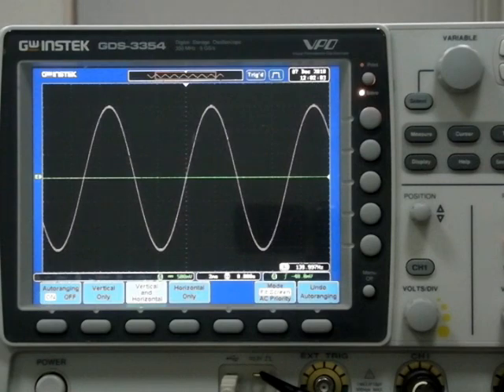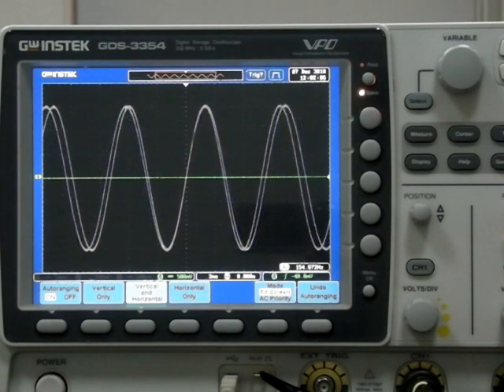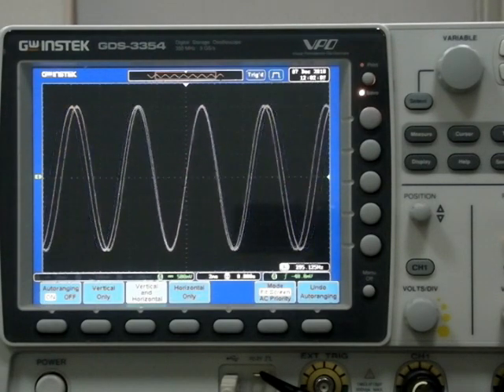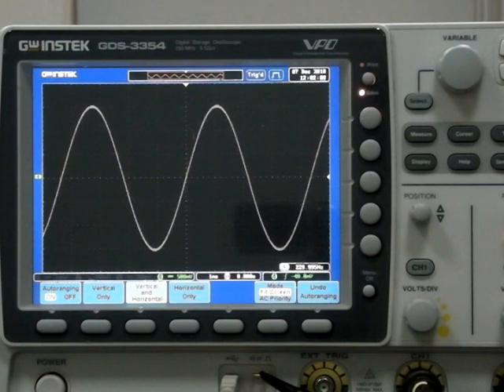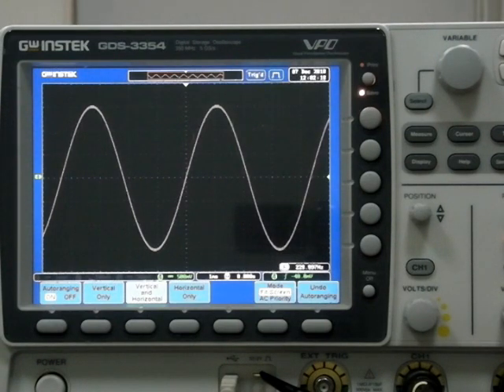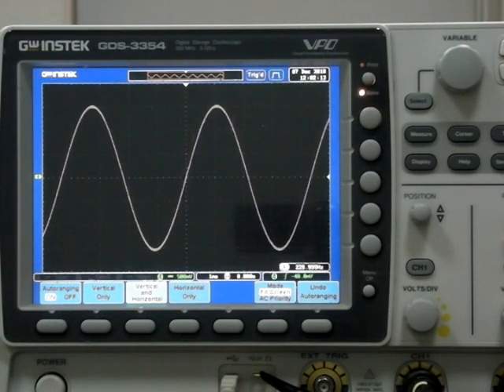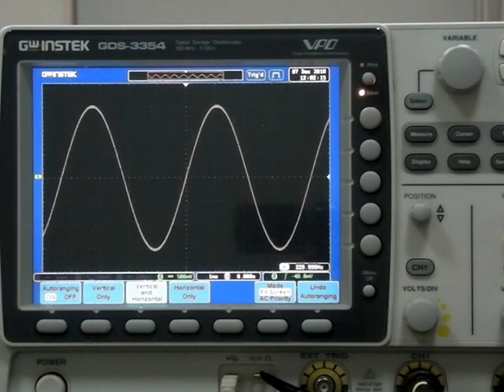When vertical and horizontal is selected, the horizontal and vertical range is adjusted simultaneously. If the Waveform amplitude or frequency is adjusted arbitrarily, it is automatically adjusted to the best scale for the display, saving a lot of valuable test time.